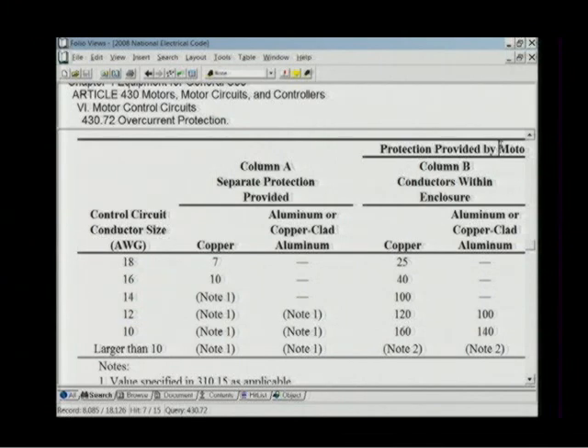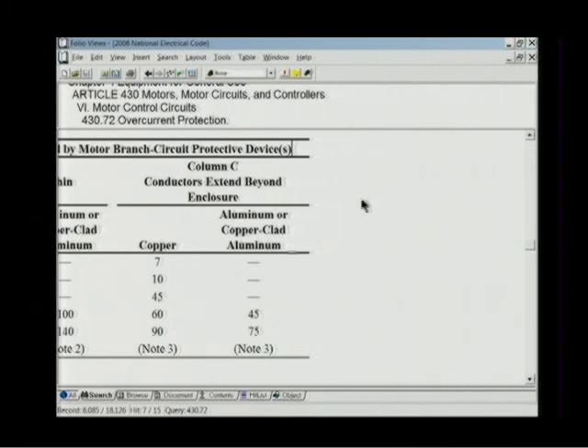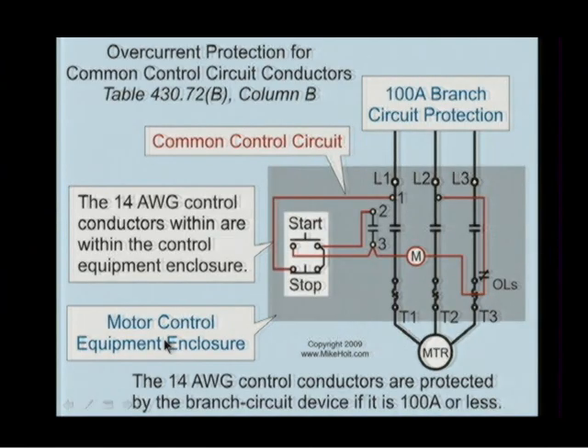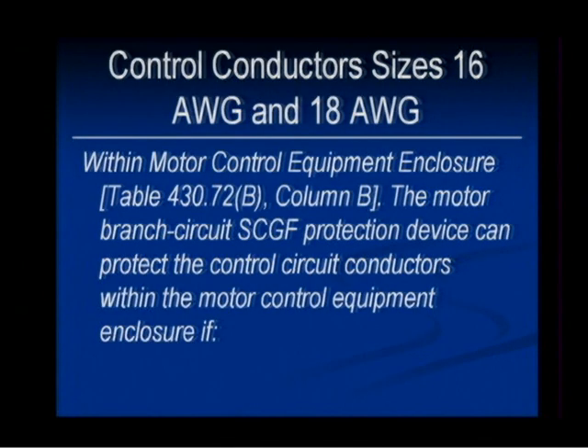But if we are extending it beyond, then you can see that it's 7, 10, 45, 60, and 90, which we'll talk about. So we can use the branch circuit protection device to serve as the protection of the control circuits, depending upon the size of the conductor, the size of the conductor relative to the size of the protection, and whether or not the conductors leave the enclosure or stay in the enclosure. We're not going to deal with staying in the enclosure. We're going to deal with when they extend beyond the enclosure.